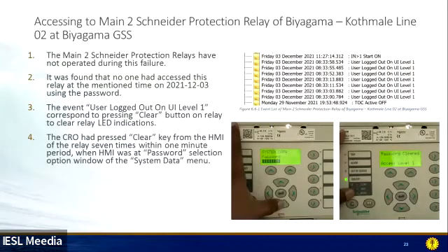The main two Schneider protection relay did not operate during this failure. That is also an important thing, because there was a discussion, there was some comment that main 2 had operated, but in this particular line tripping, the main 2 relay never operated, only the main 1 relay operated. So even if somebody had accessed this relay, it never tripped the line. And it was found that no one had accessed this relay at the mentioned time on 2021-12/3 using the password.